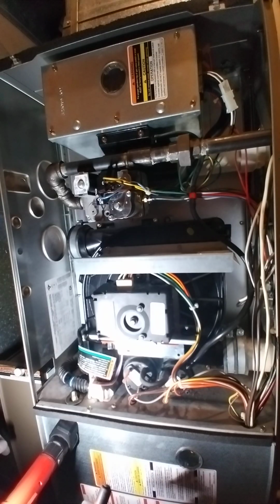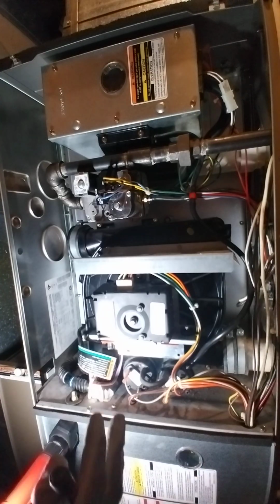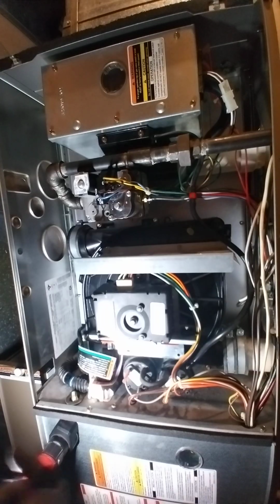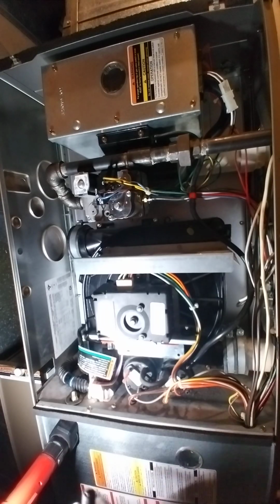And if you do some Google searching and some YouTube searching, the most common cause is a blocked return air vent, whether it's just dust or forgot to take the labels off the filter or something like that. And what that leads to is a high temperature in the furnace itself that trips the high temperature limit sensor. That's from what I found to be the most common cause, but I was confident that wasn't the cause in this case. The filter was brand new. I even tried running the furnace without the filter in it just to confirm things.